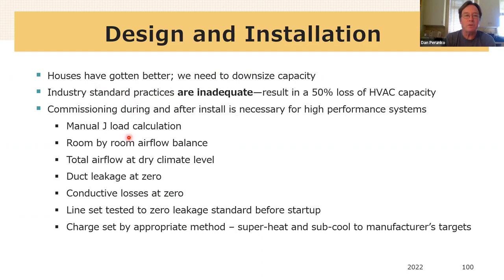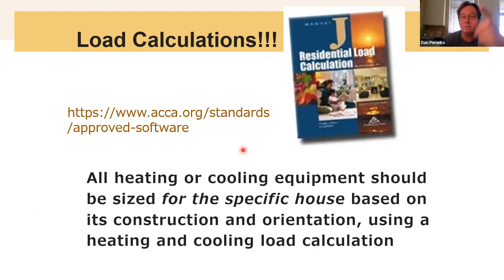So these are all things that really need to be thought about, right? So we have load calculations are required. We need to know how much energy we have to deliver to different portions of the house, what the total airflow for a system needs to be. We need duct leakage to be zero, conductive losses to be as close to zero as possible. The line set testing that I just mentioned and refrigerant charge has to all sort of be considered at design and installation. Otherwise we end up with systems like we have now, which are operating at about 50% losses.